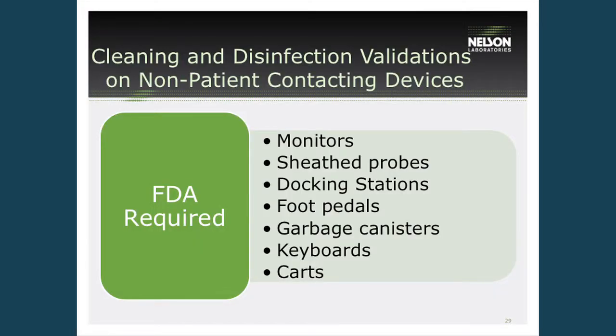Now, one of the things that has come up very recently is a very important aspect that the FDA is absolutely requiring of medical device manufacturers, and it has kind of thrown us all for a loop. They're requiring cleaning and disinfection validations for non-patient contacting devices. And this is everything under the sun, basically. We have been testing everything from computer keyboards to garbage cans to everything in between. And it's been very difficult for that testing to occur, if you can imagine testing garbage cans for cleaning validations.